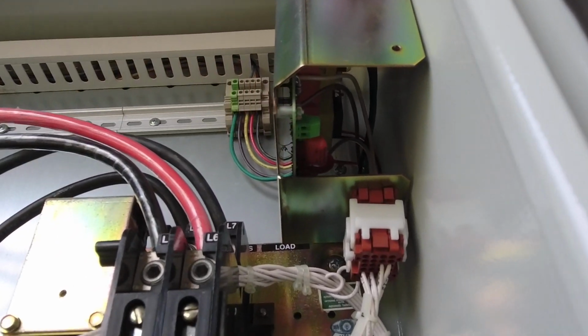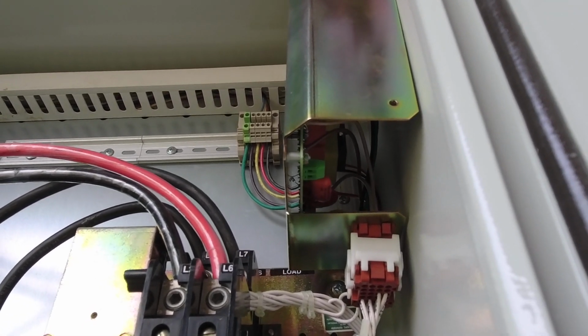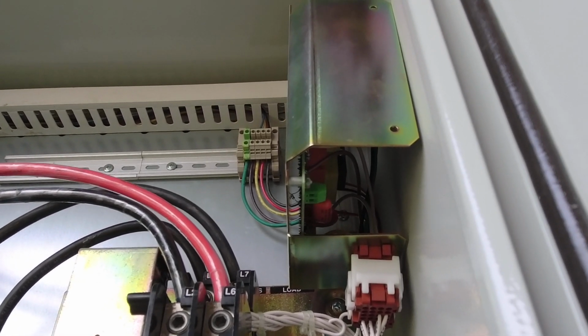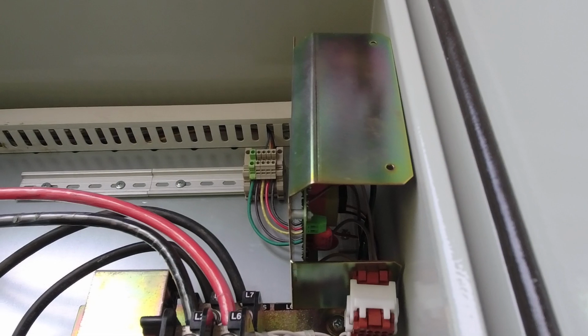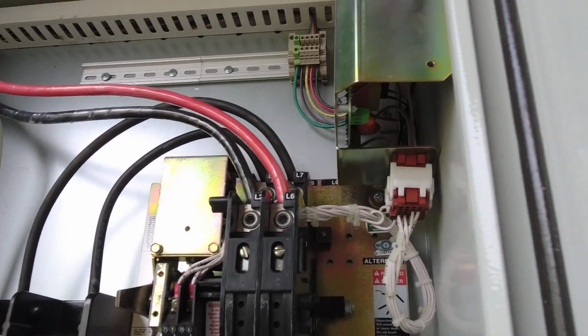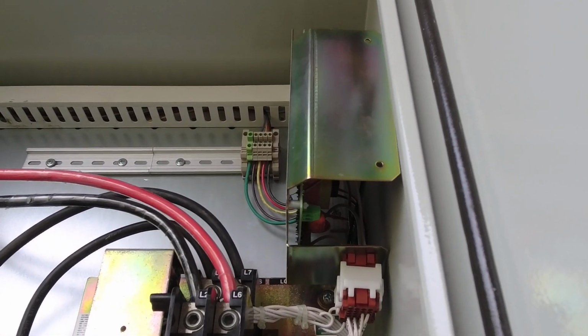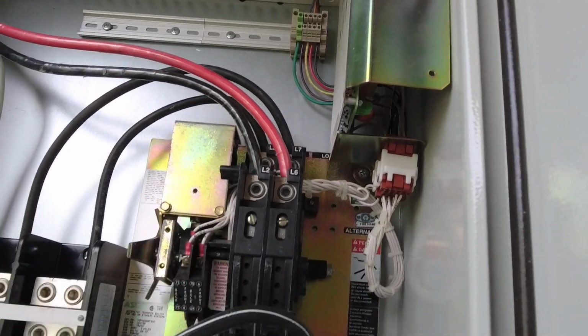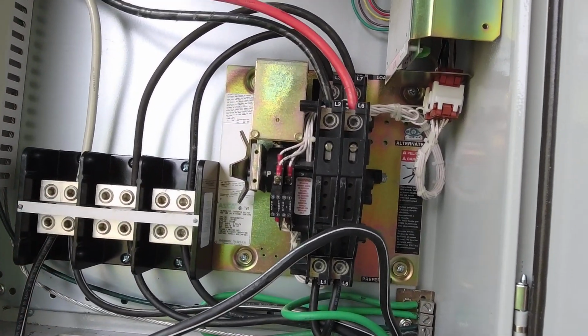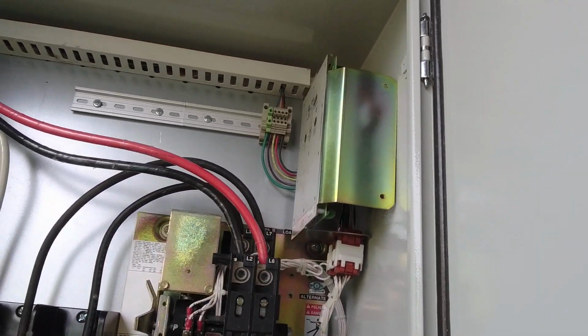I did determine what that terminal block is, that's just 10 volts DC, period, all day long. It doesn't turn off or on when the thing functions. Well, actually, we don't know that for sure because we didn't function test the transfer switch. Maybe that goes away when it throws to alternate. We have yet to find out, so more to come on that.